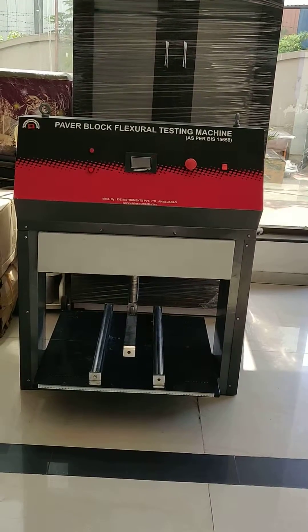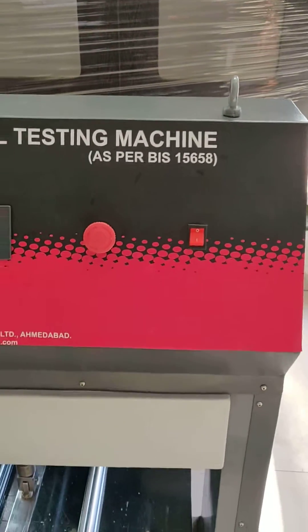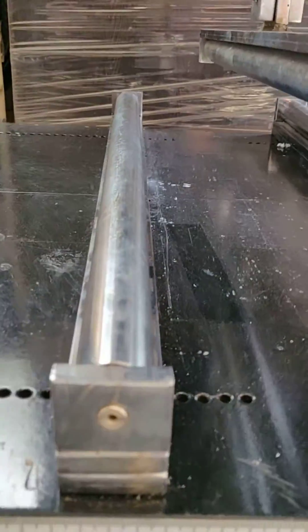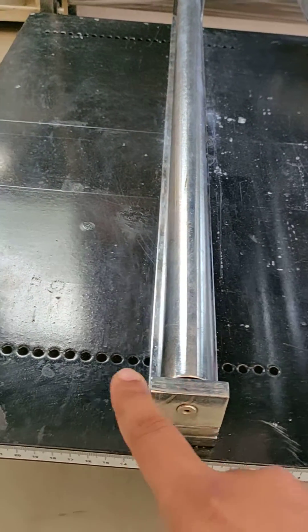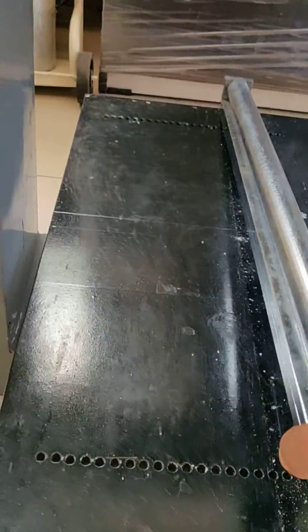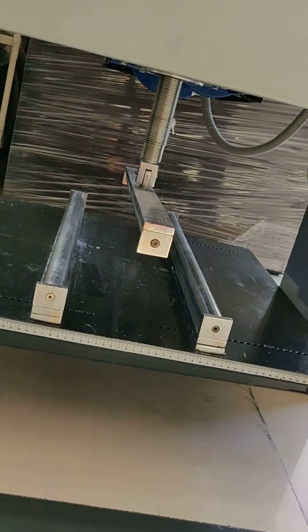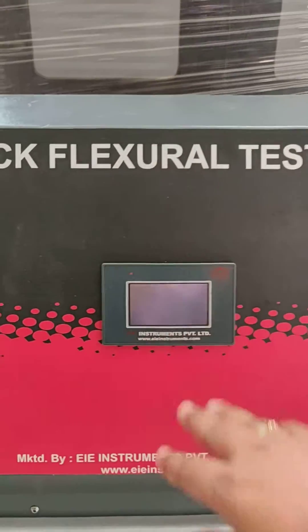This is a paver block flexural testing machine, as per IS15658. Three rollers are there with 30mm diameter. You can adjust the size of the roller by adjusting the pin holes — this roller comes with a pin and you can adjust. The upper roller will come from upside down and pressurize the paper block until it breaks. We will get the result on this touchscreen.